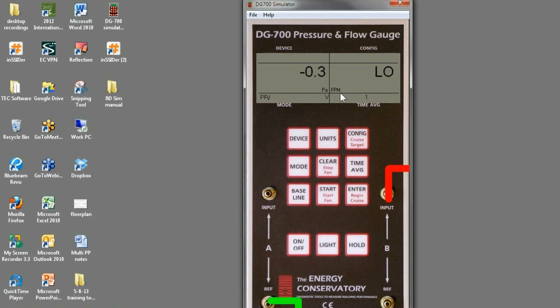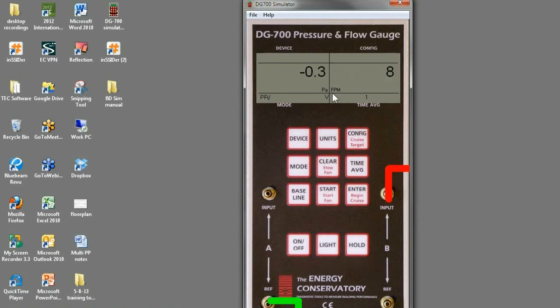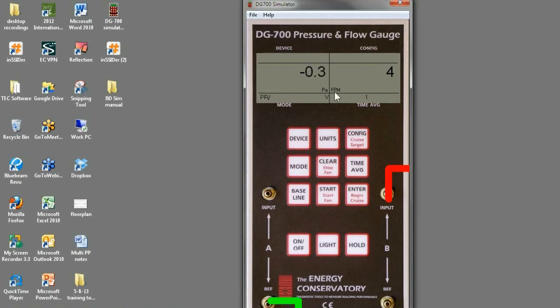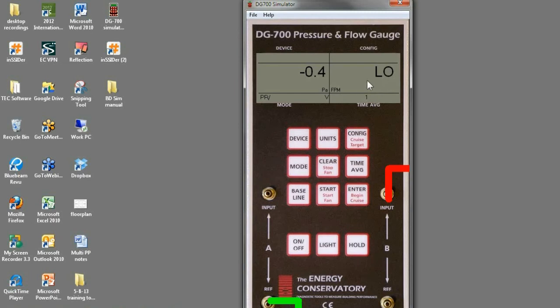So what's being displayed on channel B is velocity in feet per minute. And then to get cubic feet per minute, you would multiply that by the square footage cross section of the duct that you're measuring. So square feet of the cross section of the duct times feet per minute would be cubic feet per minute.